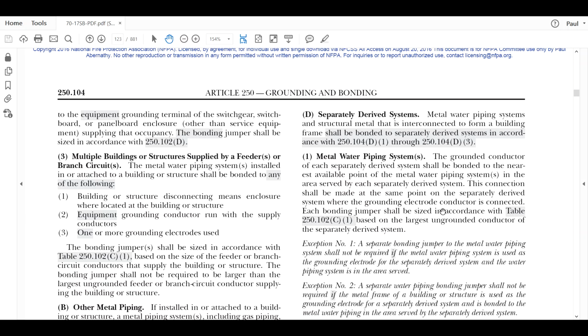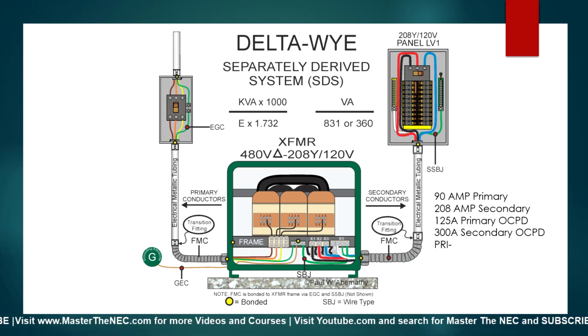And then it says each bonding jumper shall be sized in accordance with Table 250.102(C)(1) based on the largest ungrounded conductor of the separately derived system. All right, and we're not going to get into the exceptions. You can read those. We're always going to talk about the general rule here. Okay, and basically we can kind of know what we did before. Since we were dealing with this system here, and let's say over here was the metal water pipe, since the conductors were 350, then we go to 250.102(C)(1), and we'll know that it's actually the same size as these. So it would be a 2 gauge. So we'd run a 2 gauge, and that's what we'd run over to the water pipe ground. And that's how we do it. Again, it's based on these conductors, utilizing 250.102(C). Okay? All right. So now let's go back and look at the code a little more.